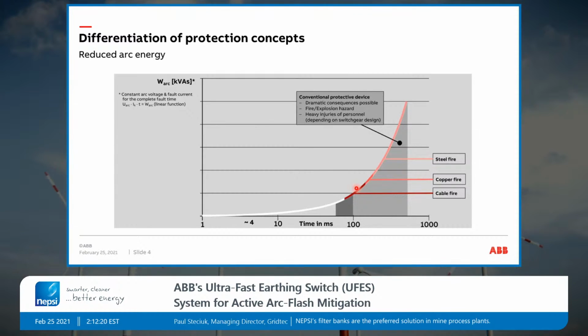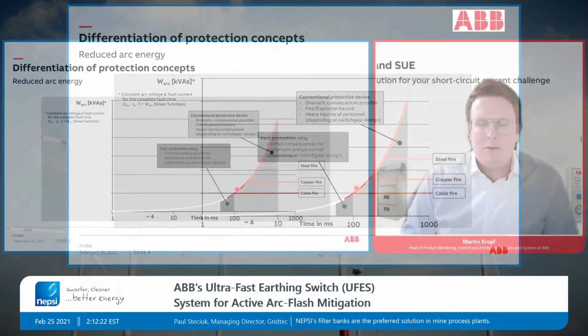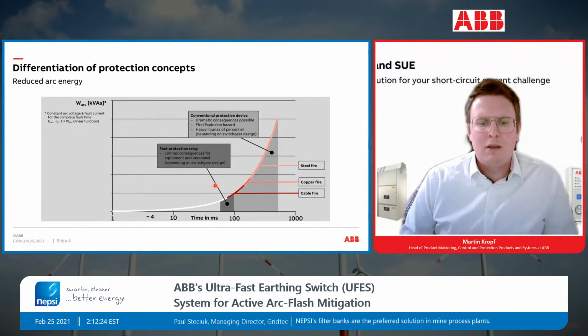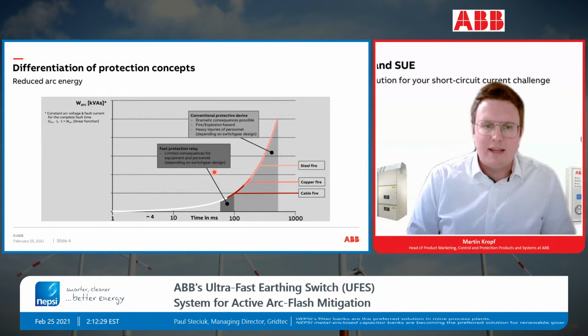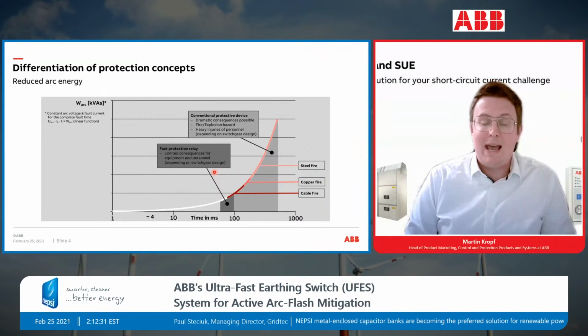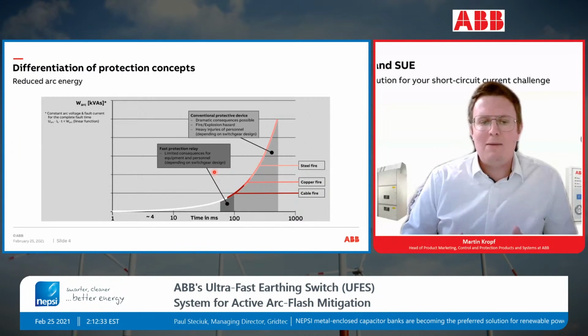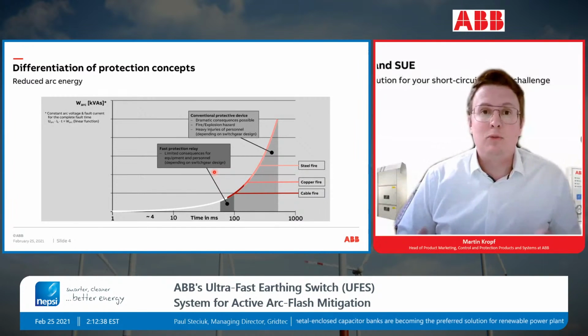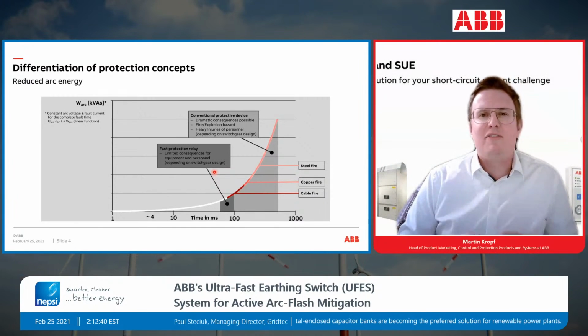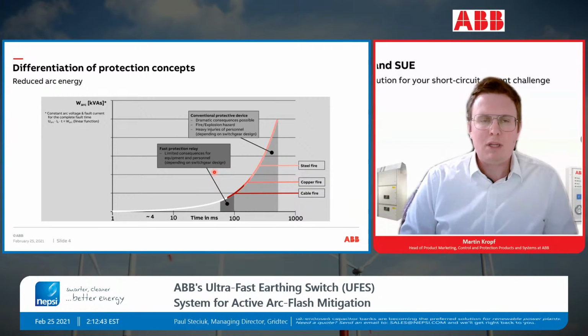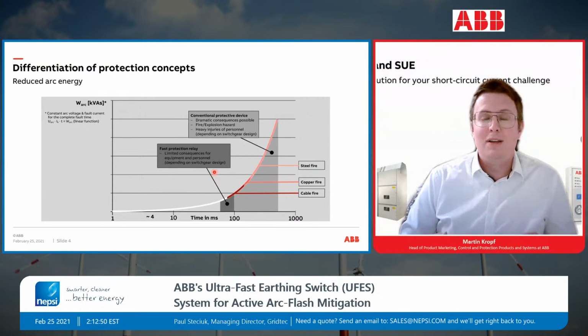So there are actually two steps where you can improve. The first step is that we can try to be faster in detection. So we choose a fast protection relay. This is definitely helping, because we have a relay in place which is optimized with light sensors, for instance, to be very fast in detecting the internal arc. Relay times in that area are 2 to 3 milliseconds. So after 2 to 3 milliseconds, you know it's an internal arc, and then you trip the breaker.